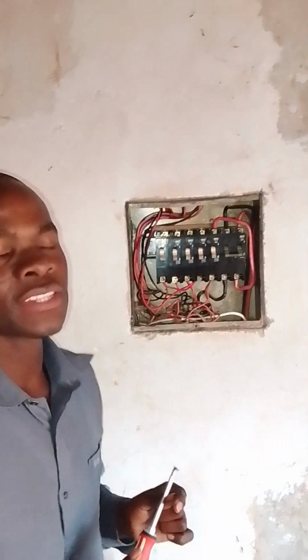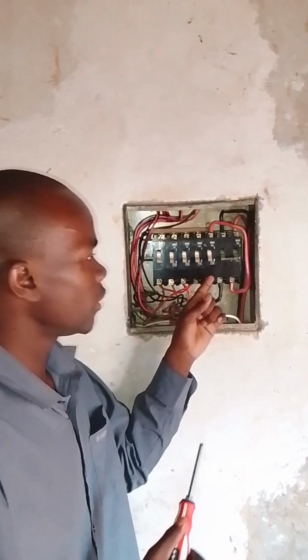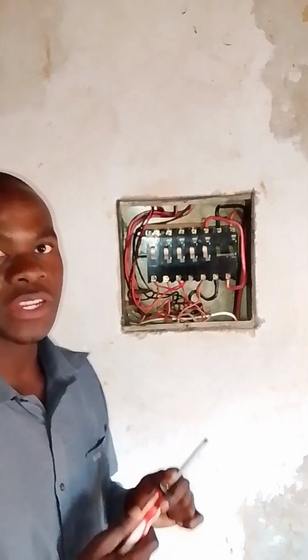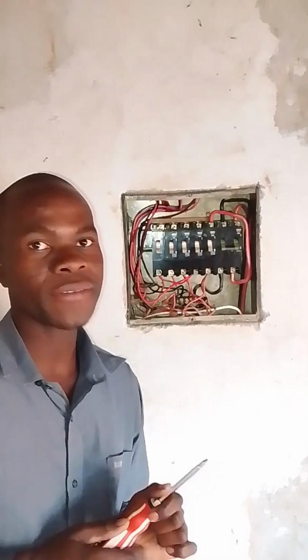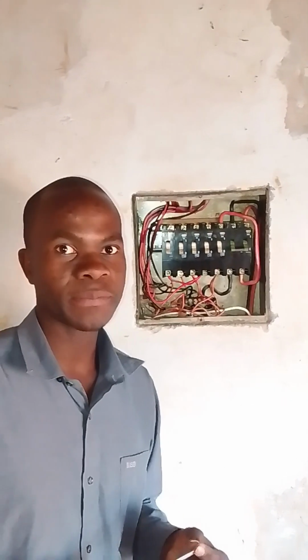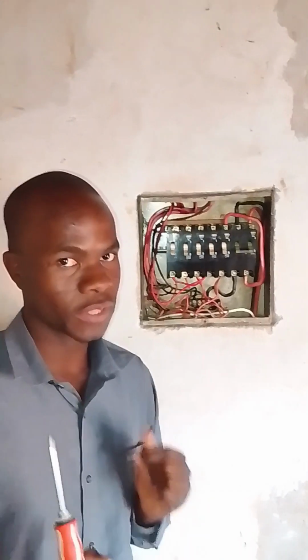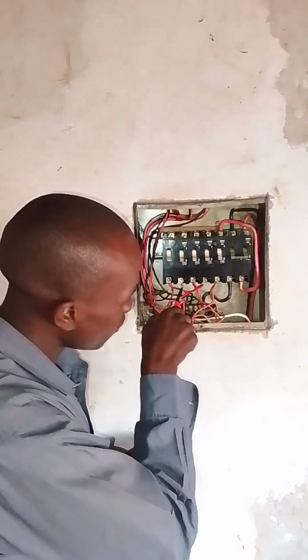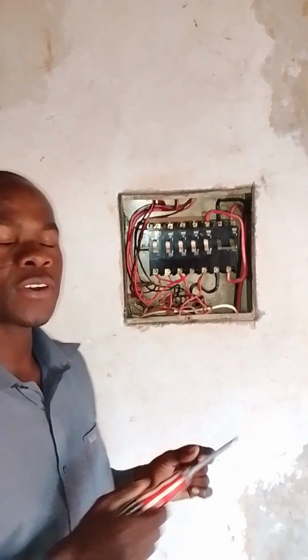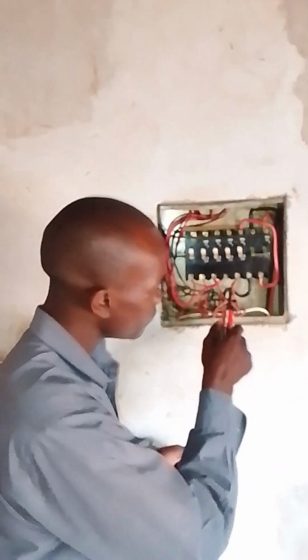After this, we want the loads to have current. So what we do is that for the lights, you have to get the 1.5 millimeter cable. That is for the lights. Like this one is the 1.5 millimeter cable. And then for the plugs, we get a 2.5 millimeter cable.